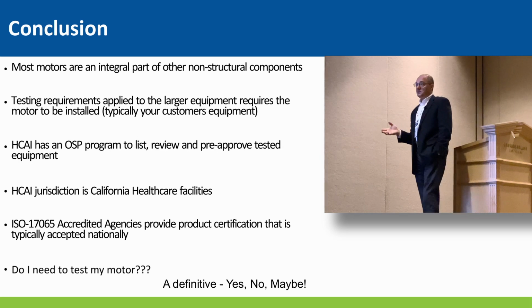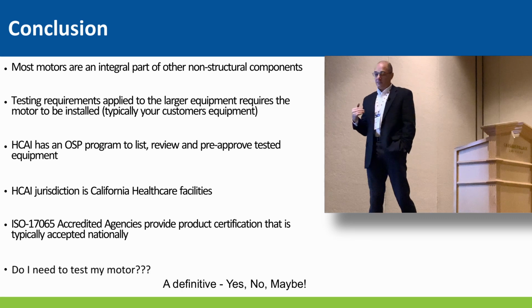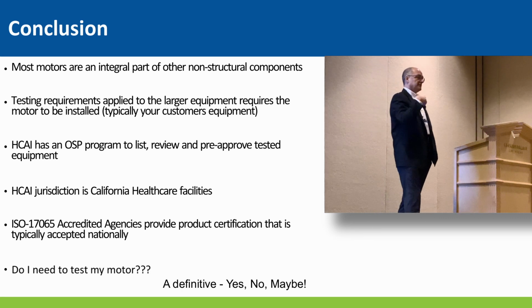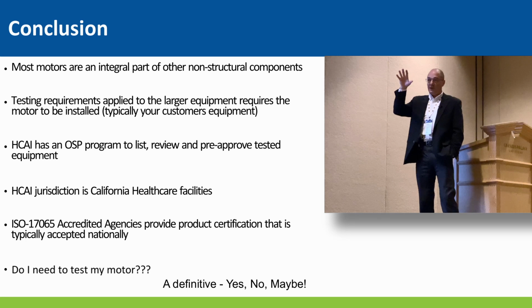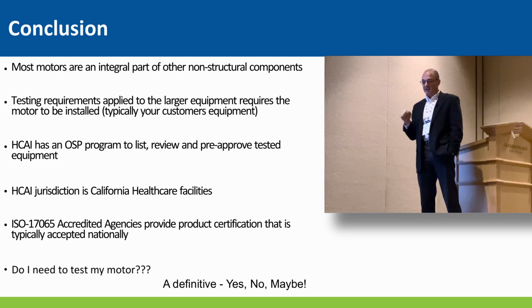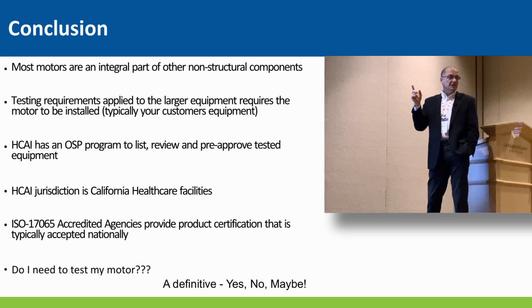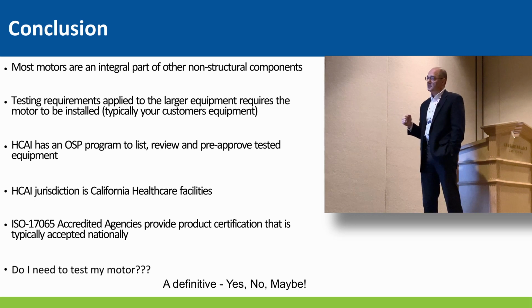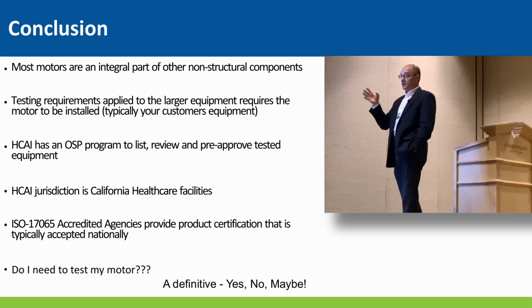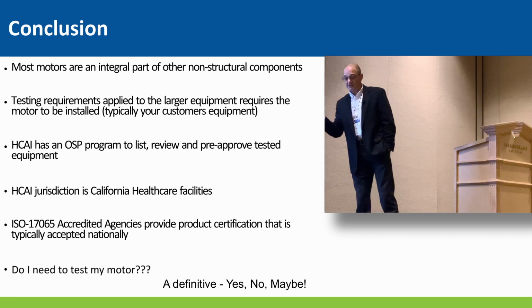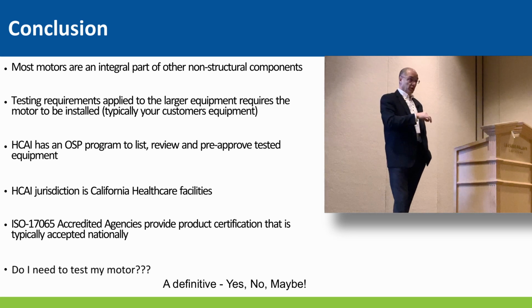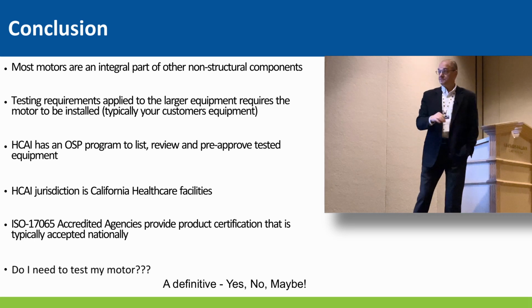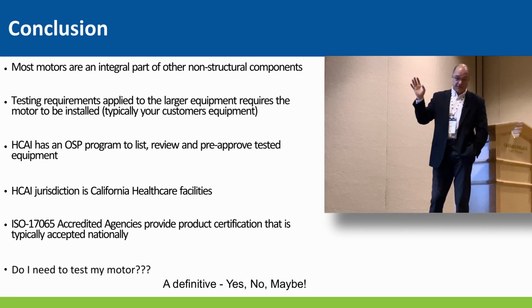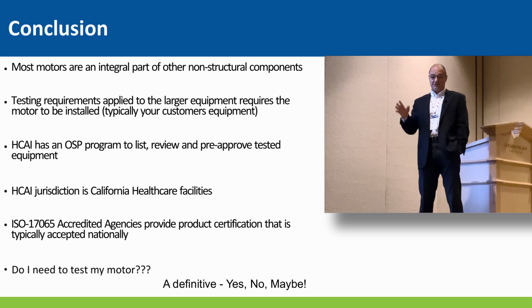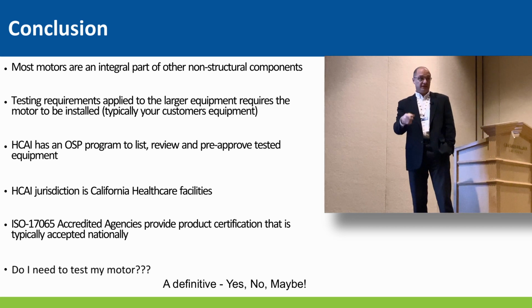HCAI has what's called an OSP program where they'll list your equipment if you've met all their standards and tested to them. They'll put it on their website so you have it listed. It expires every second code cycle, so you can't go past the next building code. Remember, that's only for California healthcare facilities — most jurisdictions will accept it, but they don't have to. So you could go to OSHPD, spend tens of thousands of dollars, build your equipment, get it tested and certified, then go sell it in another seismic area, and they don't have to take it.